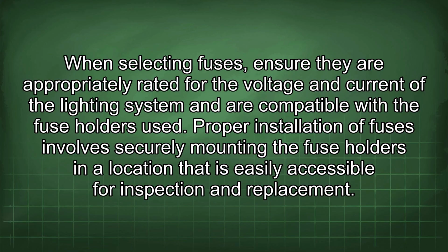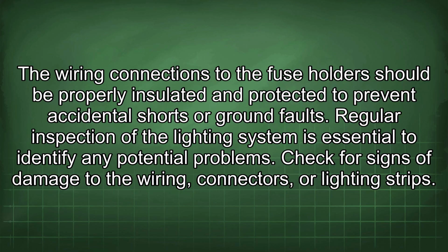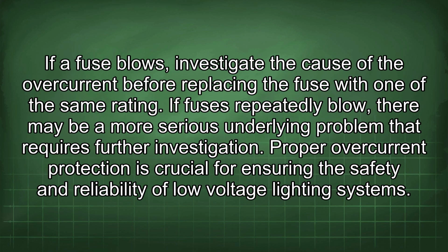Proper installation of fuses involves securely mounting the fuse holders in a location that is easily accessible for inspection and replacement. The wiring connections to the fuse holders should be properly insulated and protected to prevent accidental shorts or ground faults. Regular inspection of the lighting system is essential to identify any potential problems. Check for signs of damage to the wiring, connectors, or lighting strips. If a fuse blows, investigate the cause of the overcurrent before replacing the fuse with one of the same rating. If fuses repeatedly blow, there may be a more serious underlying problem that requires further investigation.